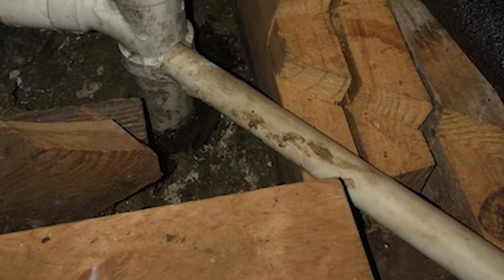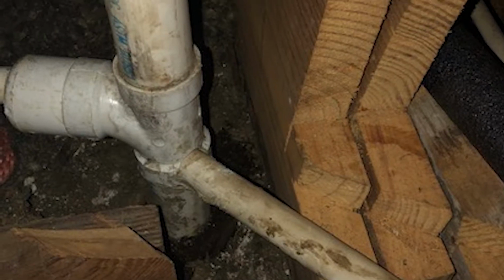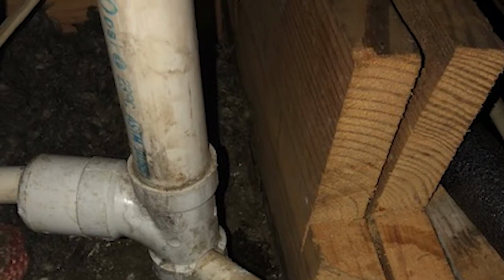Right there. All right? So it's about a half gallon a day, he says, being captured through towels and buckets right now, which is, at least he's capturing it, right? I can feel moisture off the connection in the attic, but only dampness, and the seal appears to be secure and caulked properly, all right? So I cut a hole behind the sink, and I can see condensate dripping when the compressor kicks in. So, Tom, what do you suggest for Richard?